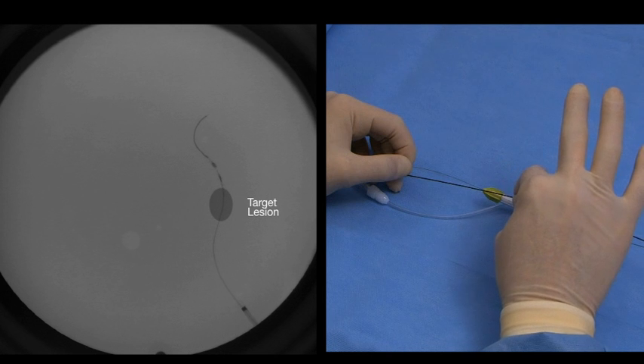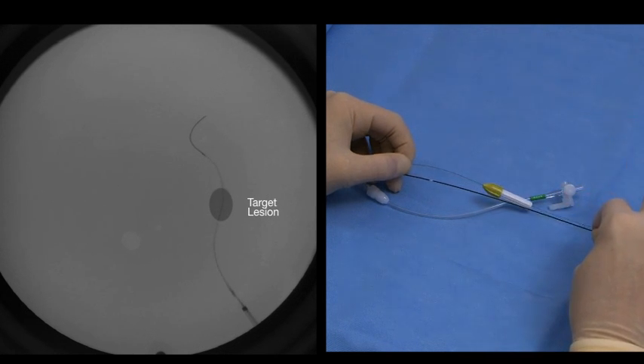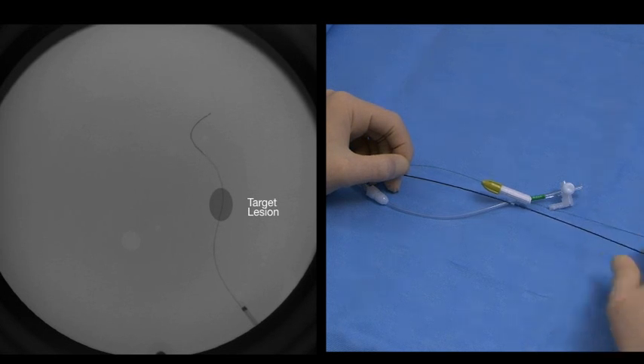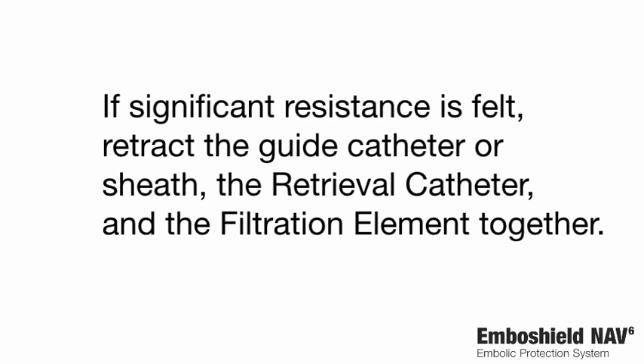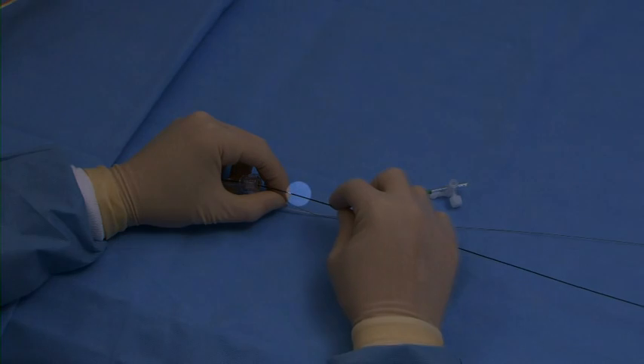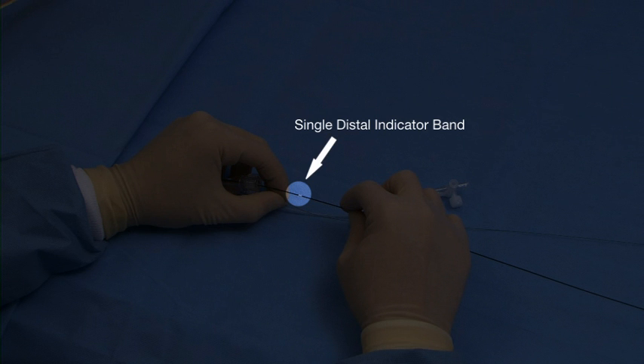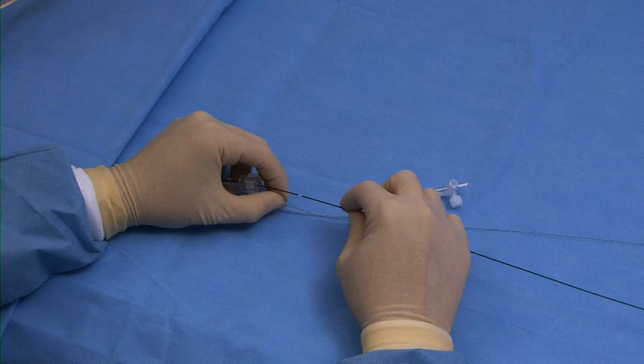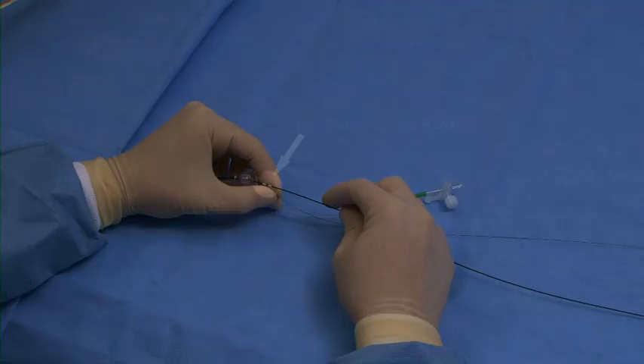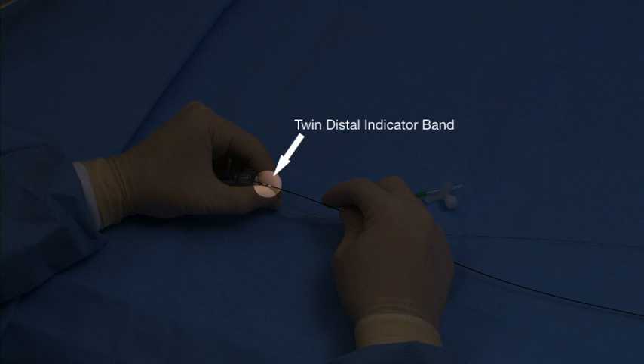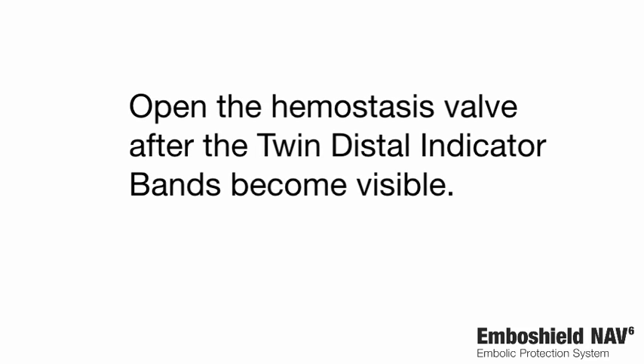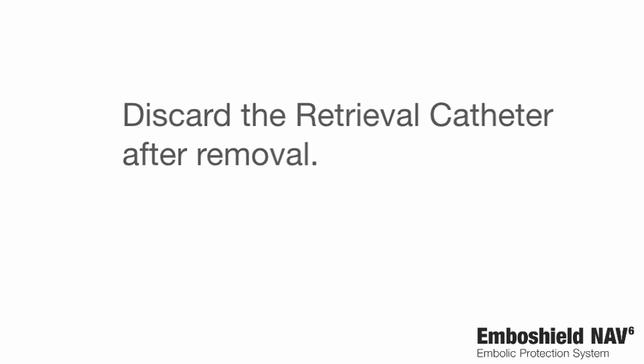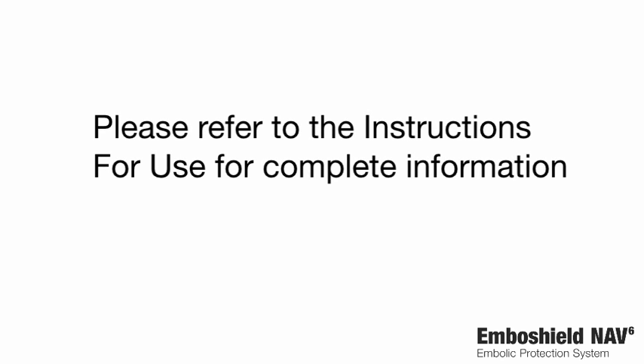Retract the retrieval catheter over the bare wire, or remove the retrieval catheter and the bare wire together as one unit. If significant resistance is felt, retract the guide catheter or sheath, the retrieval catheter, and the filtration element together. Notice the single distal indicator band is positioned 15 centimeters from the rapid exchange exit port, and the twin distal indicator bands are located 5 centimeters from the rapid exchange exit port to aid catheter retrieval. Open the hemostasis valve after the twin distal indicator bands become visible. Discard the retrieval catheter after removal. Please refer to the instructions for use for complete information.